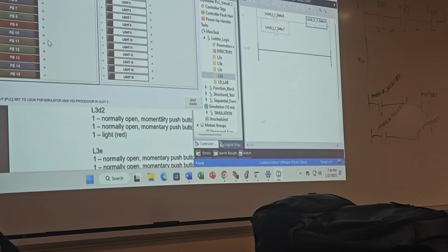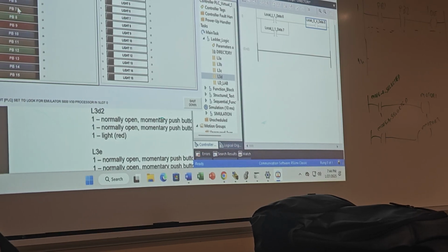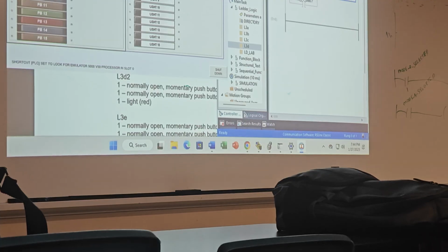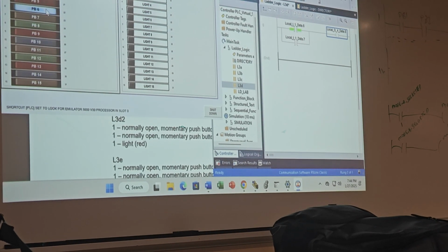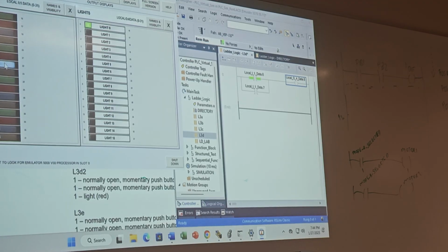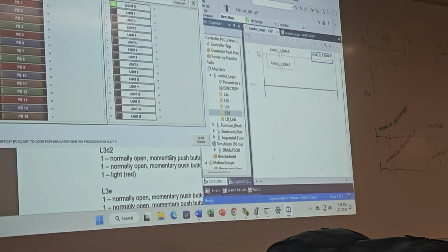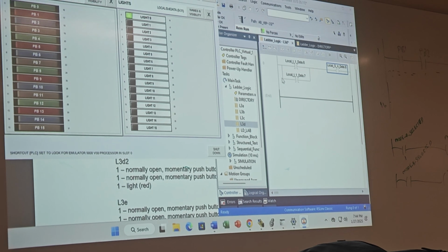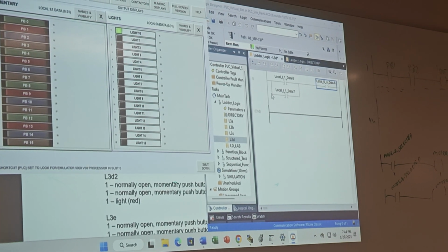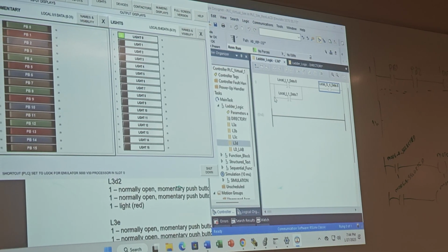Now, I didn't call it, right? Yeah, it's not called. So this one should turn on light 8. So let's try. Yeah, not working. If you see that output is not energizing, it's because there is no energy here. To make the circuit close, one side should be a 24 or 12, the other side should be a 0 to close the circuit. That's why it doesn't.